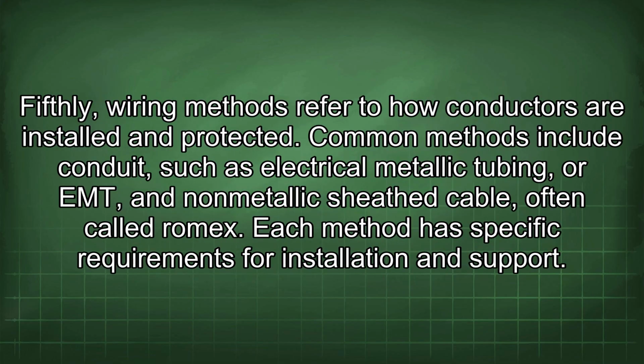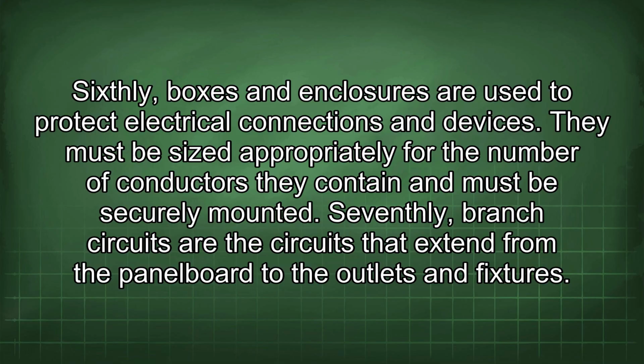Fifthly, wiring methods refer to how conductors are installed and protected. Common methods include conduit, such as electrical metallic tubing, or EMT, and non-metallic sheath cable, often called Romex. Each method has specific requirements for installation and support. Sixthly, boxes and enclosures are used to protect electrical connections and devices. They must be sized appropriately for the number of conductors they contain and must be securely mounted.